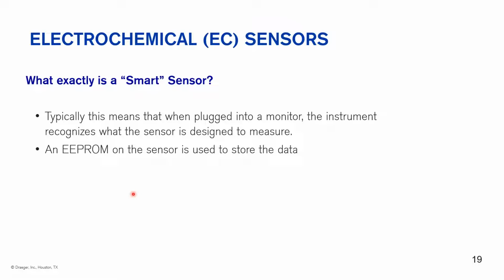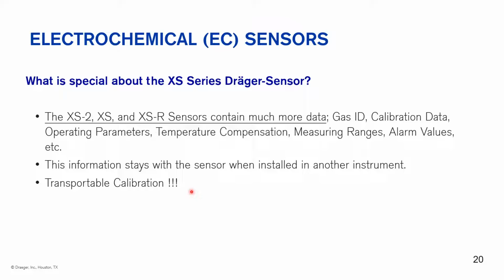Hopefully we didn't miss too much, but smart sensors in the industry, generally smart sensors have a little circuit board on them that has information about the sensor. So when you plug it into the instrument, it will recognize the type of sensor it is and upload that information into the instrument. Our XS series of sensors, we do have smart sensors for the XS, which was again for our X-am 7000. And these held quite a bit of data, and the calibration information was stored on those sensors so that you could take a sensor out of one unit, put it into another, and get it up and running without actually having to calibrate it.